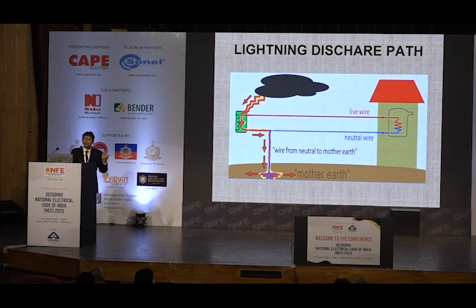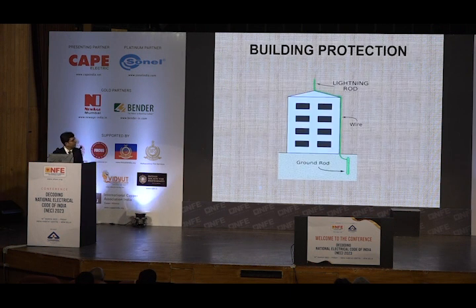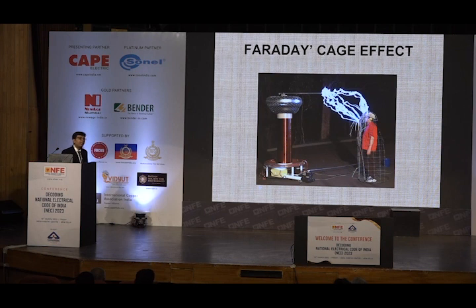Then comes your building. Lightning protection needs a proper down conductor, and the down conductor must be connected to your earthing system. Last but not the least, shielding and functional earthing are governed by the fundamental rules of Faraday's law. When you shield something and allow that external discharge to go to the earth with proper connection, nothing is going to harm. This is depicted by that picture.